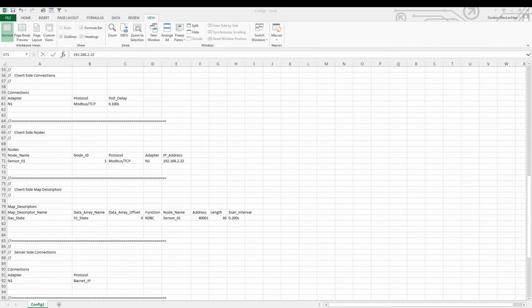This brings us to the workhorse of the configuration, which is the client-side map descriptors section. In the client-side map descriptors section, we're mapping all of the data from Sensor 1 into data arrays. So the way you want to read the lines that are here is to start in the middle, basically, towards the right-hand side.